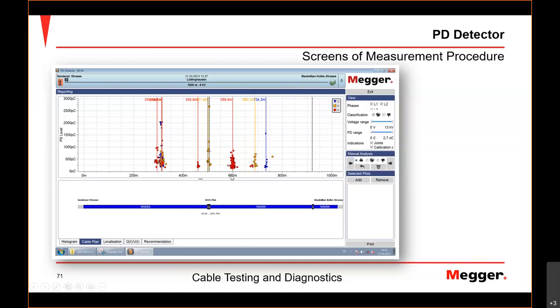At least there is something going on. It's a paper cable, might be in the paper. But we see a level of just under 1,000 picocoulomb. But there is something going on. That cannot be normal because right here in the blank, there's nothing going on. So it must be possible to have the cable clean of partial discharge. Why is there something here? So I don't go so much by the level, but first consideration is: is there a concentration of discharges? Then it means there's a problem.